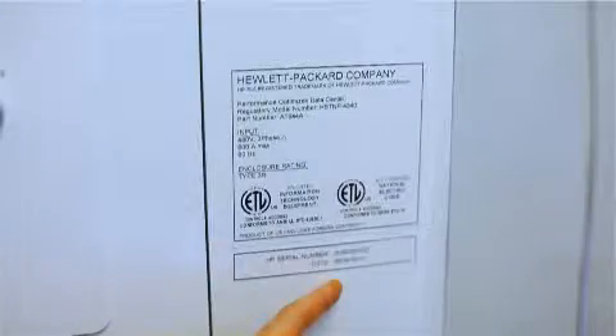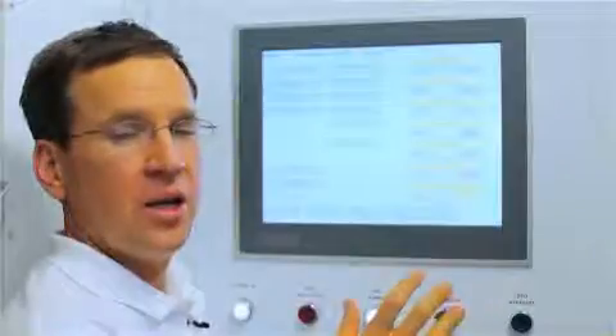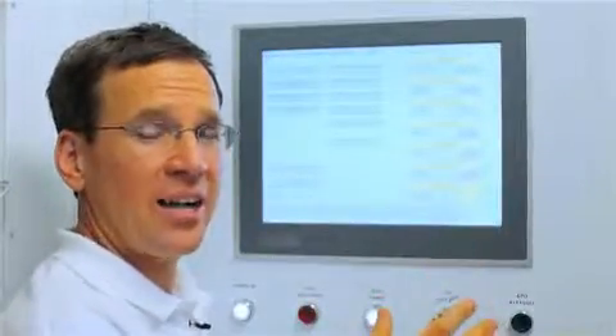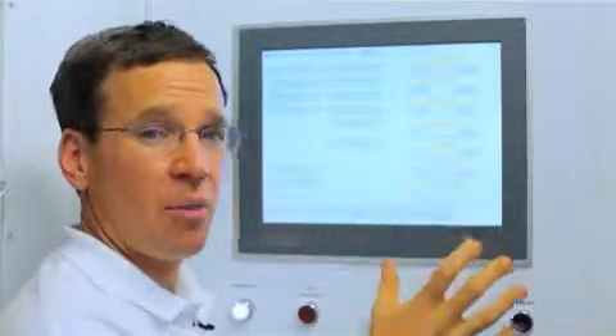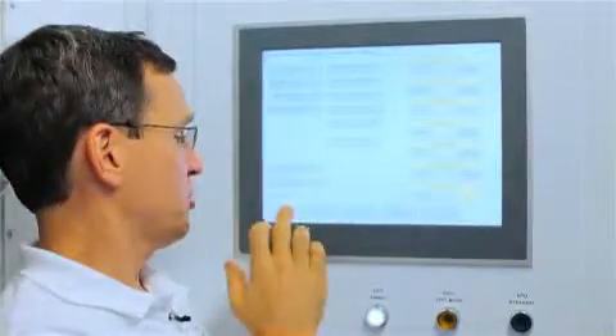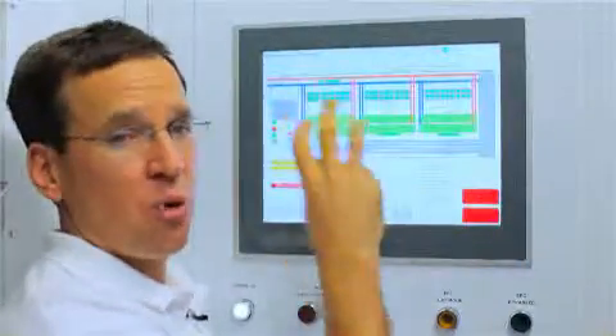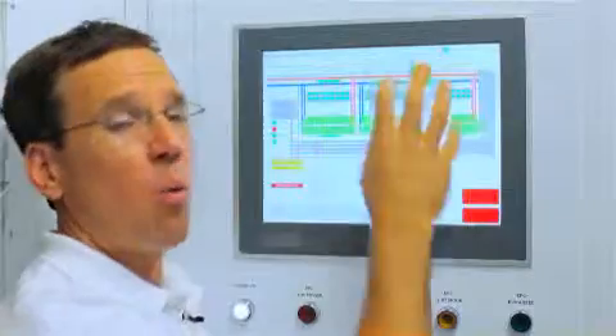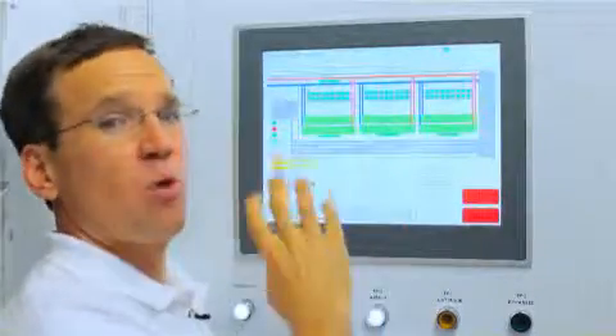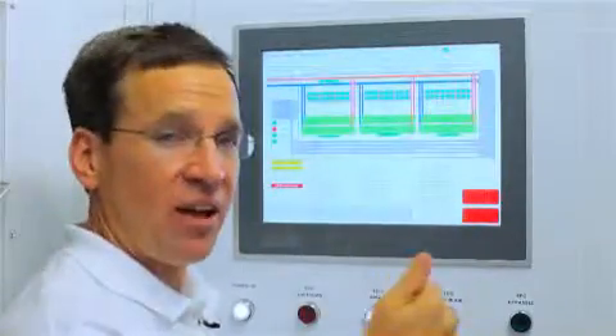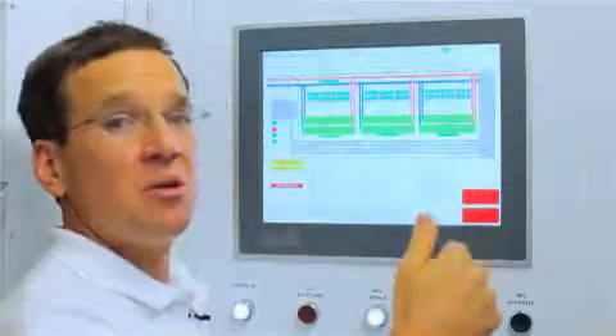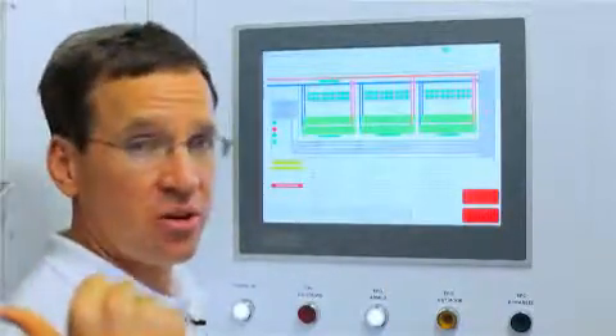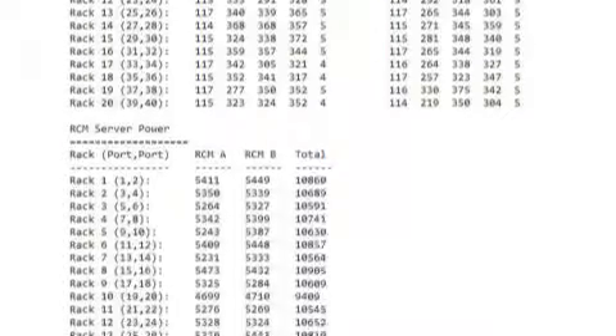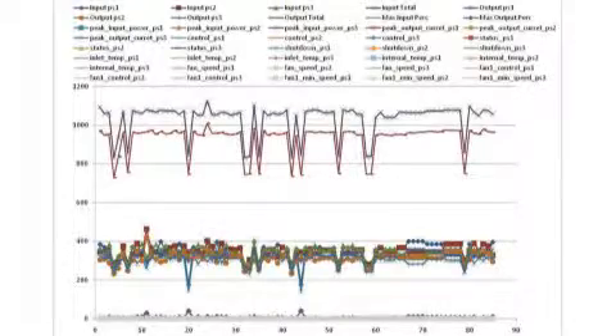The HP-POD is not a building. Per codes like UL, it's actually a piece of information technology equipment. New for this 3rd generation pod is our touchscreen environmental control system. It monitors things like temperature, pressure in the hot aisle, cold aisle, water, power, and it can report all that and control the fans, the chillers, reach in and talk to the servers, and also look up to the transformers and switchboard at the facility level.